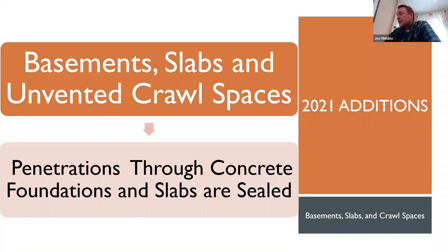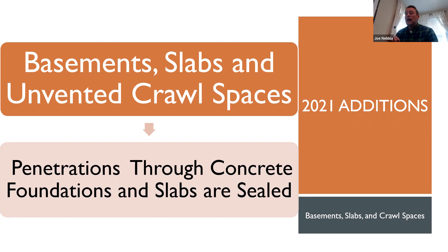One of the additions in the 2021 code: there are additional details in the air barrier installation table, one of which is that basements, slabs, and vented and unvented crawl spaces have to be sealed anywhere there's a penetration in the foundation or slab. The code already requires sealing any penetrations, but now these penetrations are specifically called out. In case anybody had a question about a pipe running through the slab, the code says yes, you do have to air seal it.